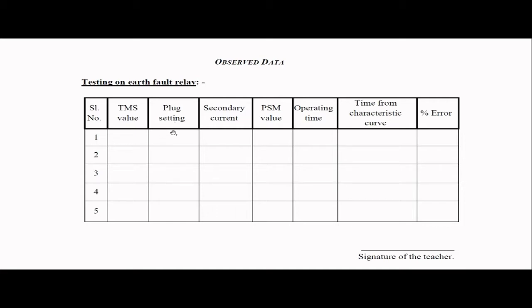Then the TMS value. TMS value is also put in the relay itself. So the TMS value for the earth fault relay is from 0.2 to 0.8. According to the requirement, the user can set the TMS value as he or she requires. Then the secondary current means how much current is flowing to the relay coil. This is directly measured from the ammeter connected in the relay.